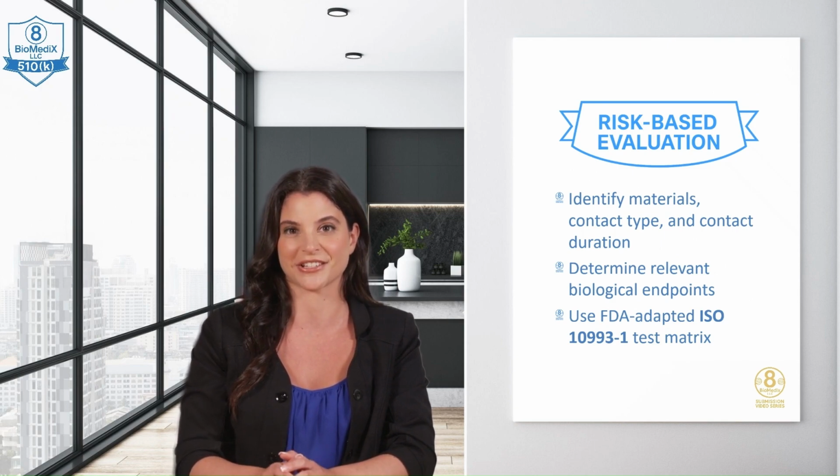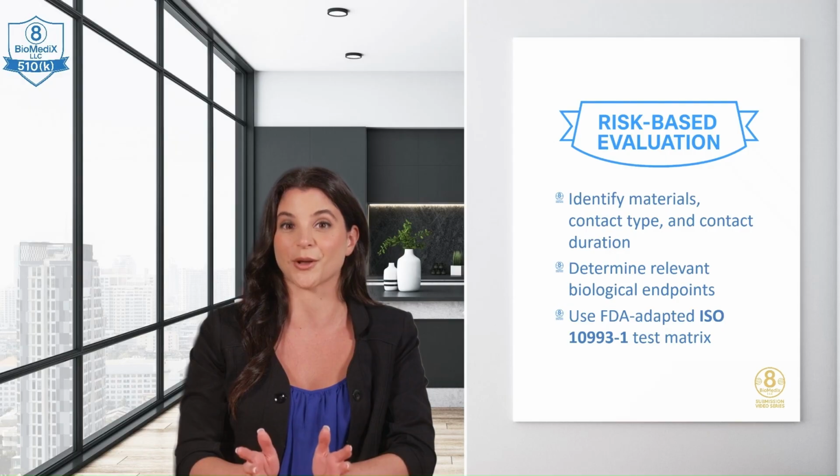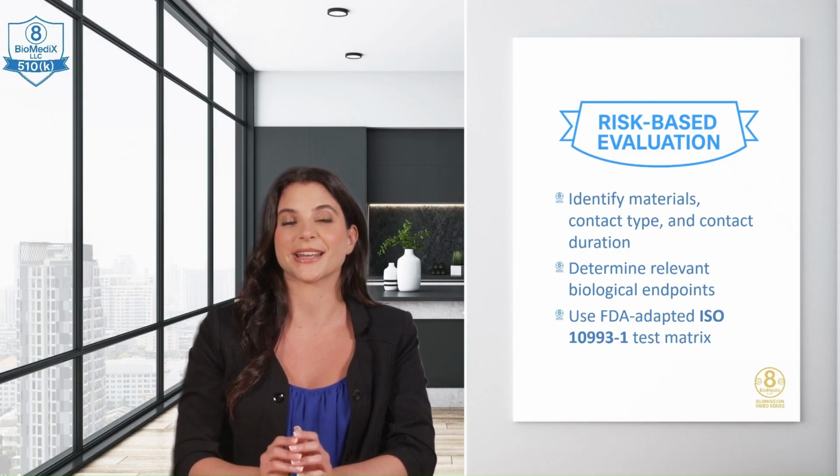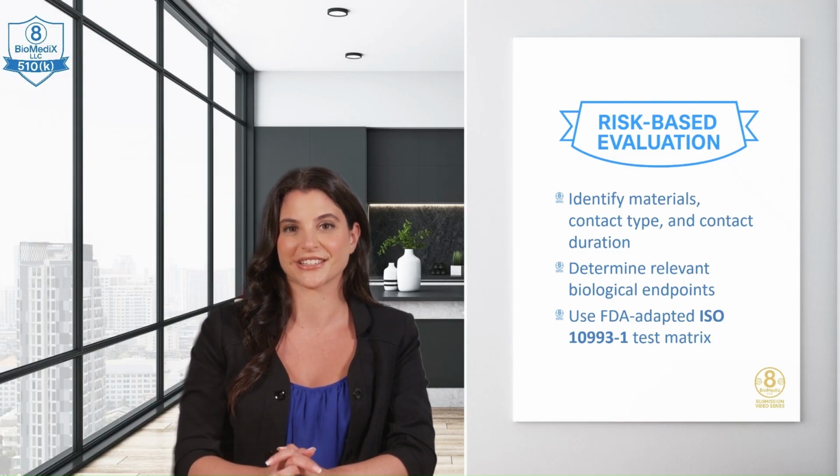The FDA expects you to assess the final sterilized device because additives, processing aids, and residuals all play a role. You'll need to list all your materials, identify the contact type, skin, mucosal, blood, and the contact duration, limited, prolonged, or permanent.